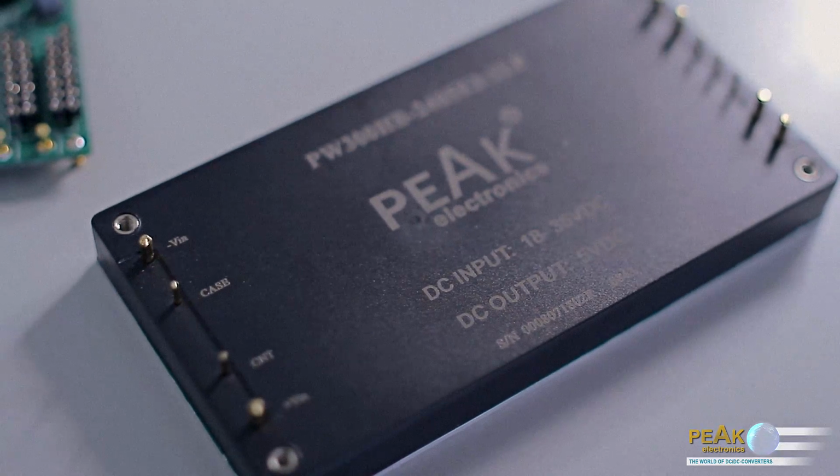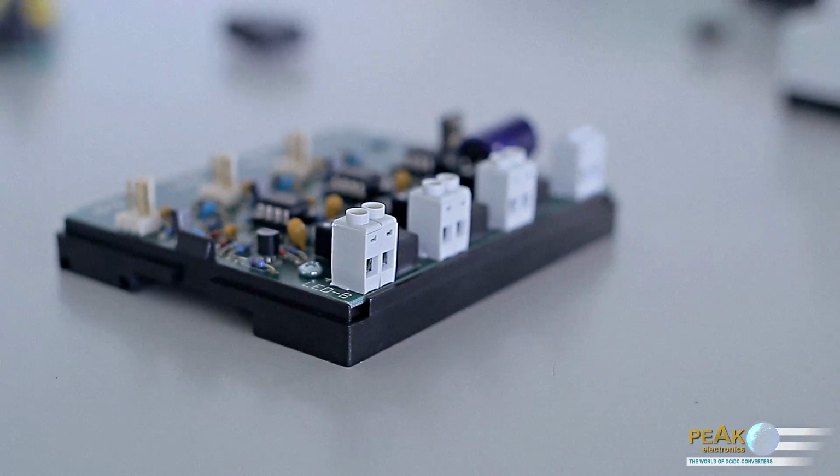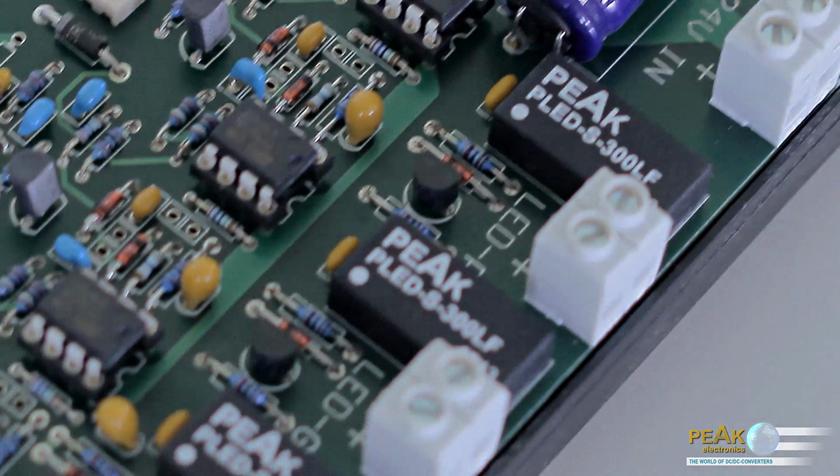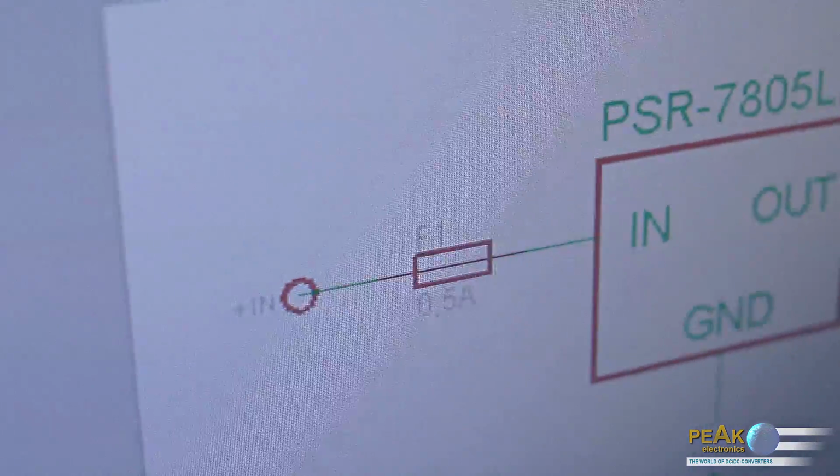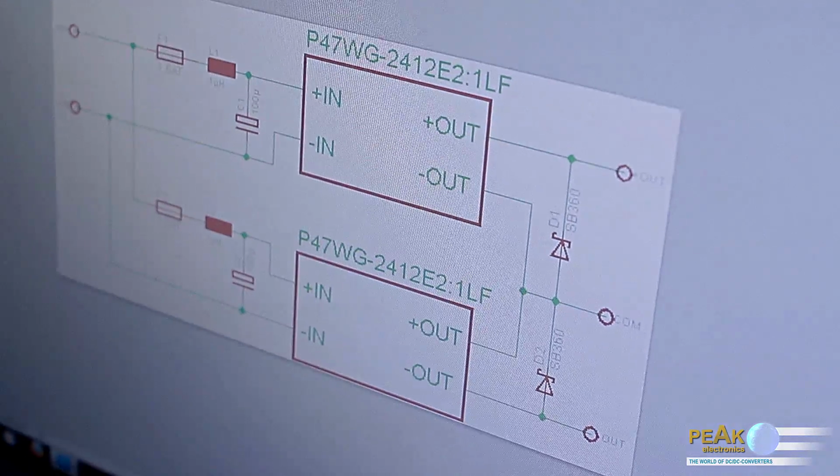Ideally, DC-DC converters are chosen, all of which can be operated with the available supply voltage. Hence, all DC-DC converters can be connected in parallel on the input side, which means that all minus inputs and all plus inputs, respectively, are connected to each other. The advantage of this is to provide each individual converter with an appropriate protection on the input side. In some applications, it can be necessary to provide LC suppression with one or several of the converters used. Thus, it can be avoided that the converters interfere with each other on the input side.